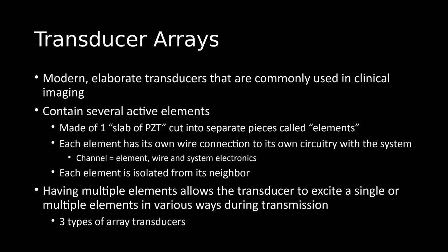But for the most part, you're going to have one piece of PZT that the manufacturers have cut up and divvied into their own little pieces, and those pieces are known as the active elements in the transducer when we're talking about array transducers. Each element is then going to be connected to its own wire system, and that's how that element talks to the rest of the ultrasound system. So each element is going to have its own electrical connection to the system.